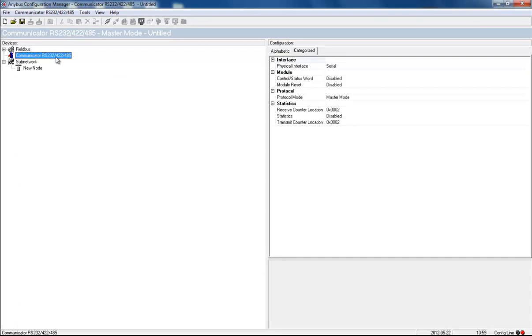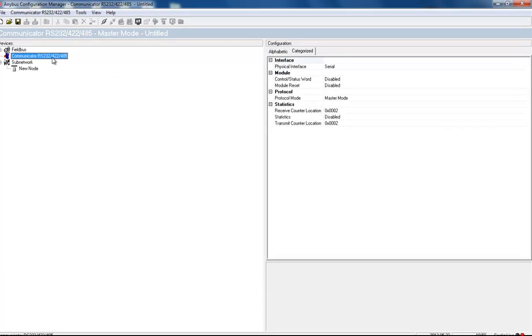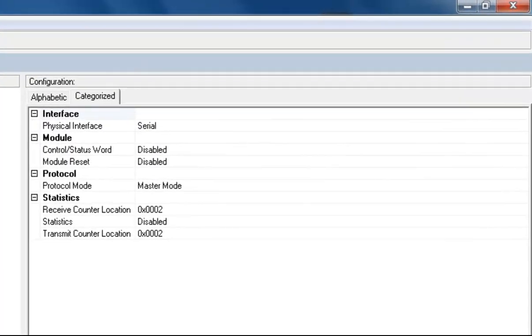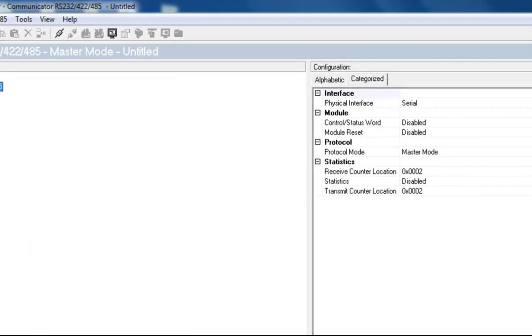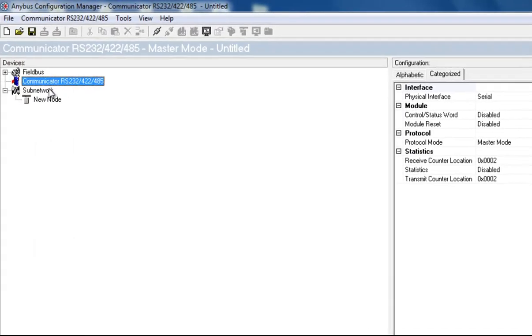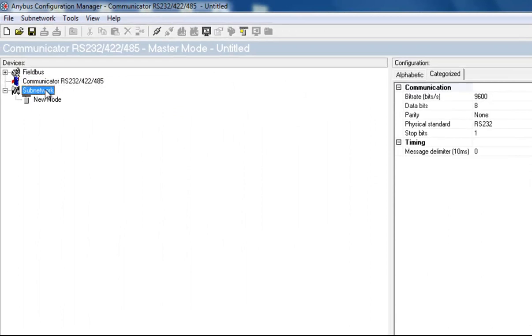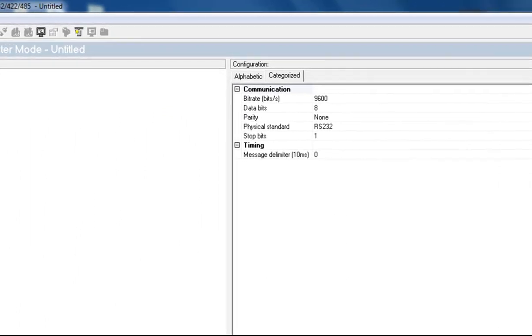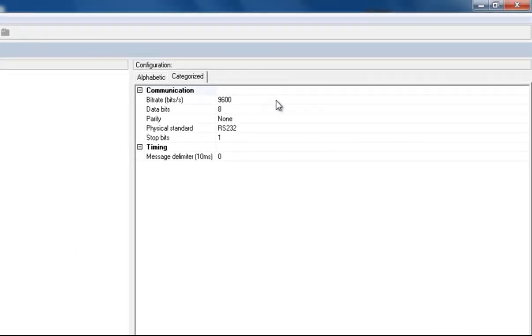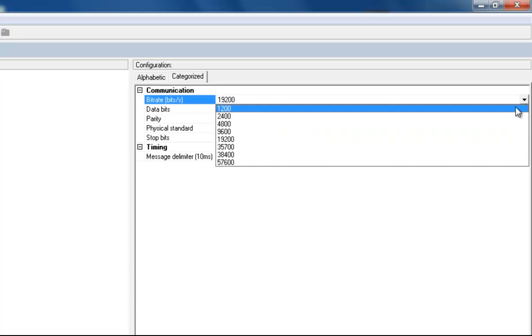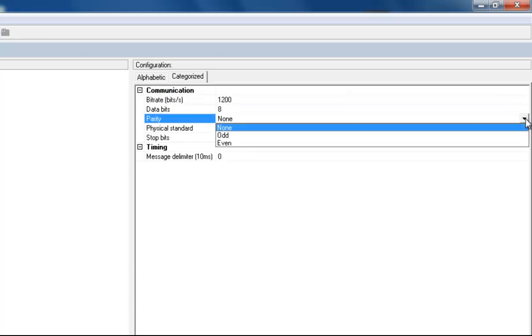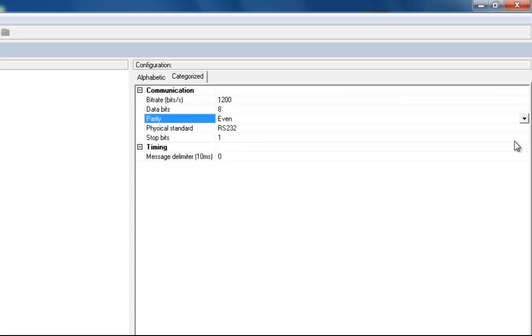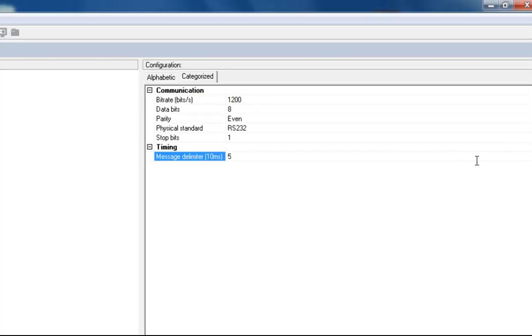I take a look at the communicator settings and can see that these are all in order. We want to use master mode since the communicator acts as master on the subnetwork. In our subnetwork, we want to specify the baud rate. We set this to 1200. The parity should be even and the message delimiter should be set to 50 milliseconds, 5 times 10.